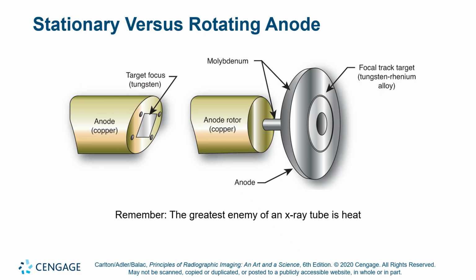The stationary anode, the best setup is a water-cooled from inside stationary anode. So you connect the collar to the high voltage, but then you have a water chamber, maybe a circulating water chamber, inside the stationary anode, and that liquid pulls the heat away from the tungsten focal spot, the stationary tungsten focal spot. Okay. And we did see at least one schematic where the Coolidge tube had a water-cooled anode.